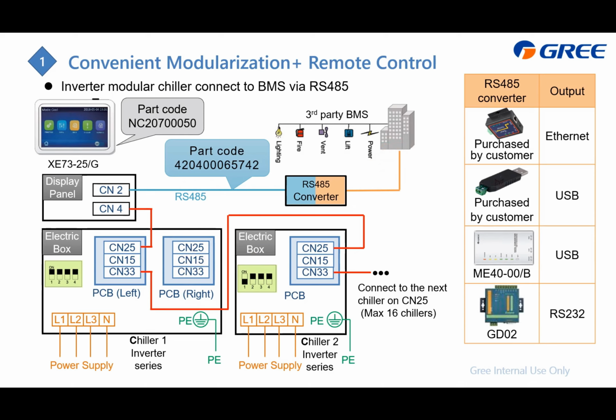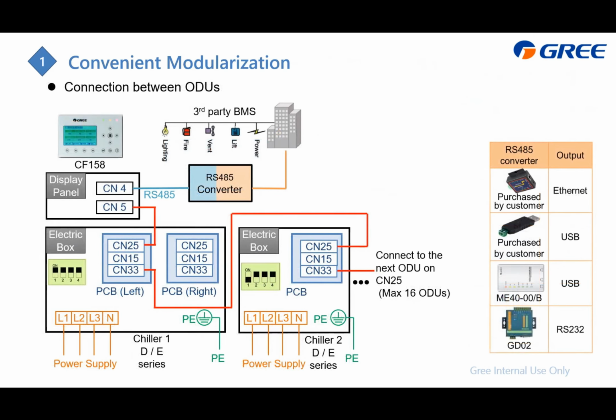And this is the modularization for the inverter series. Now for the on-off, which is the D or E series, the wiring is similar, but the controller is different, which means you can also identify it from the model. It will be CF158. But also from here, there are two ports. CN5 is to connect to the chiller, and CN4 outputs the RS485 signal for the BMS control.